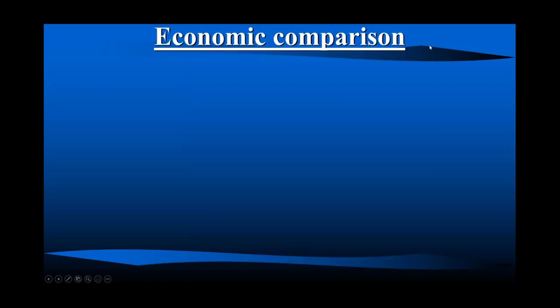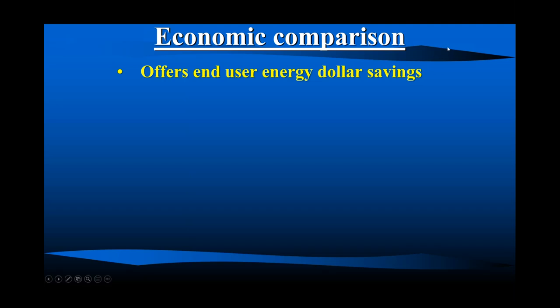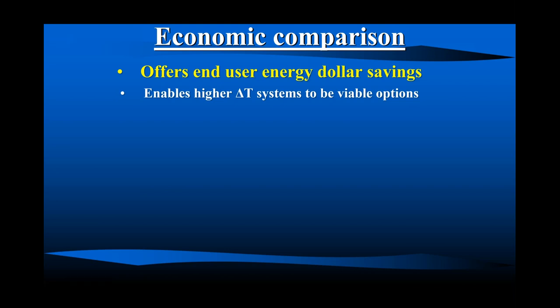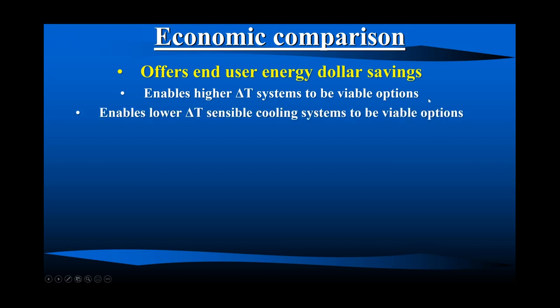Okay. So, little review. Yes, the end user will save energy dollars, right? Higher delta T systems, viable options, less problems, less people turning temperatures up or down. The future is going to involve a lot of sensible cooling only systems. Radiant and chilled beams probably are going to be much more considered for systems, especially the chilled beam with its inherent capability of ventilating the space more so.